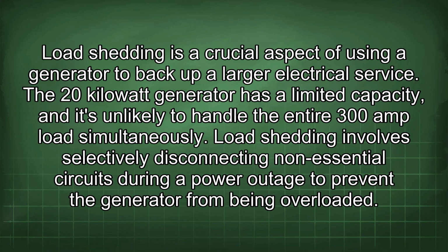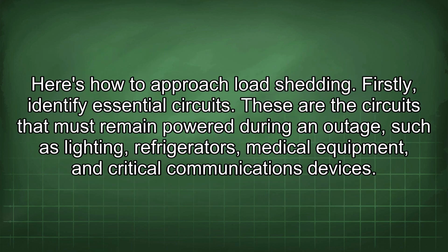Load shedding is a crucial aspect of using a generator to back up a larger electrical service. A 20 kilowatt generator has a limited capacity and it's unlikely to handle the entire 300 amp load simultaneously. Load shedding involves selectively disconnecting non-essential circuits during a power outage to prevent the generator from being overloaded. Here's how to approach load shedding.